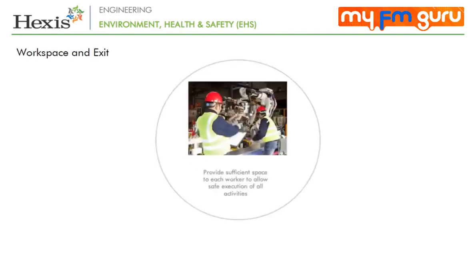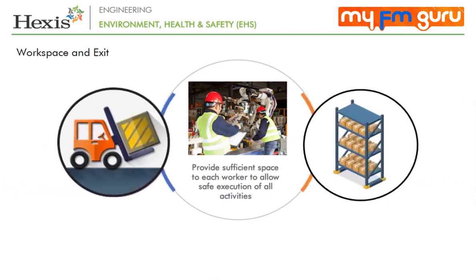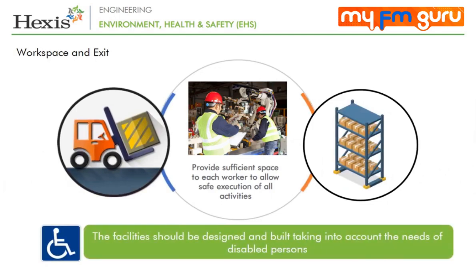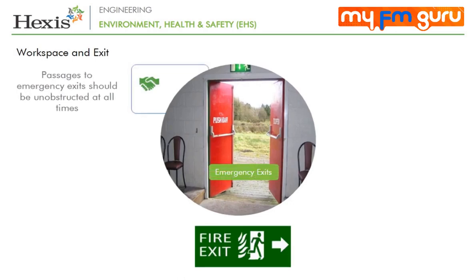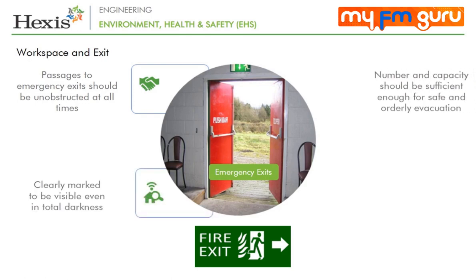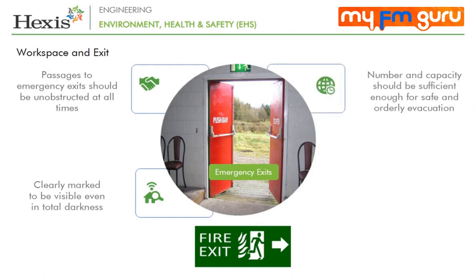The space provided for each worker should be adequate for safe execution of all activities, including transport and interim storage of materials and products. Facilities should be designed taking into account the needs of disabled persons. Passages to emergency exits should be unobstructed at all times. Exits should be clearly marked to be visible even in total darkness, and the number and capacity of emergency exits should be sufficient for safe and orderly evacuation. There should be a minimum of two exits from any work area.